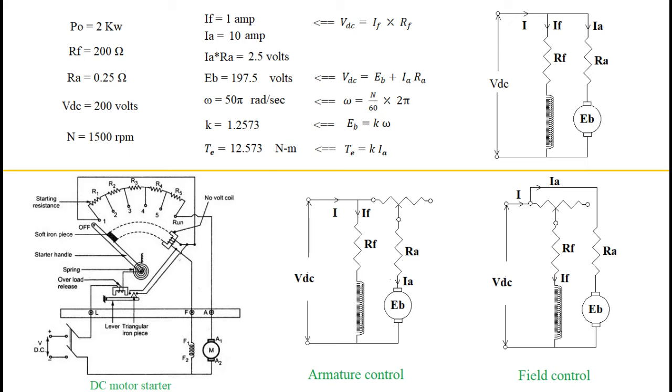Torque due to this current is only 40% of full load torque. When each 10-ohm resistor is removed from the armature circuit, torque will rise from 40% to 50% to 66% and then 100%, if we ignore back EMF. However, back EMF will still reduce the starting current.